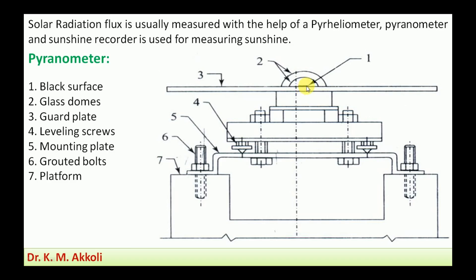Whatever radiation falls on the black surface — which is a thermopile — it generates an EMF. One junction of the thermopile is kept at the hot point, and another is kept in the shading. The EMF produced causes current to flow, and that current is measured, which is a measure of the radiation. When all beam and diffuse radiation is received, that measures global radiation; when only diffuse radiation falls on the thermopile, that measures diffuse radiation.